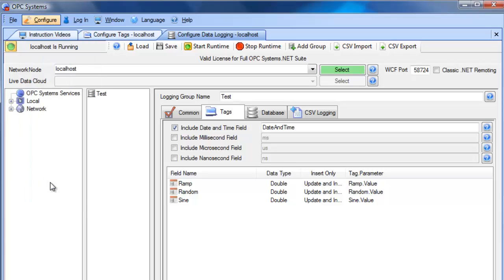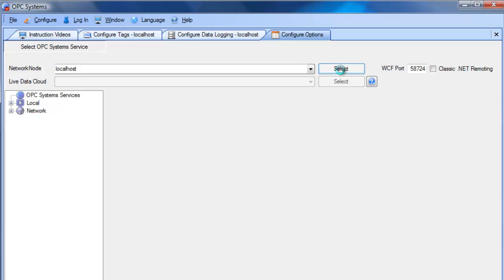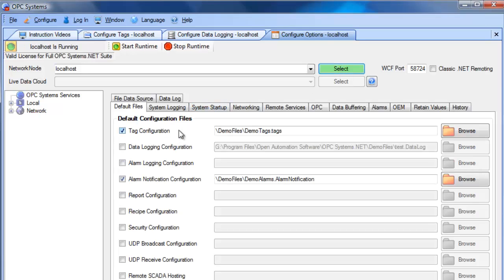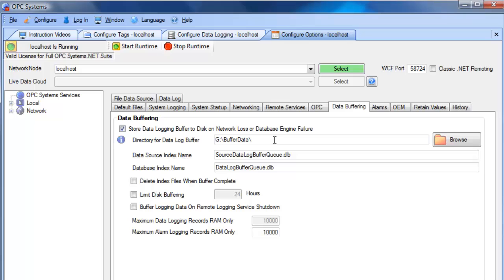Under Configure Options, you can access the data buffering feature. Select the local service under Configure Options to see the default tag configuration file. You can also set up the default data logging configuration file. Under the Data Buffering tab, specify a drive and directory to generate binary files when there is a network problem logging values to a remote database engine or if the database engine is unavailable. During any kind of network loss, files will be buffered into this directory — even for days or months — and when the connection is restored, all values will be transferred to the database one by one with no data lost.